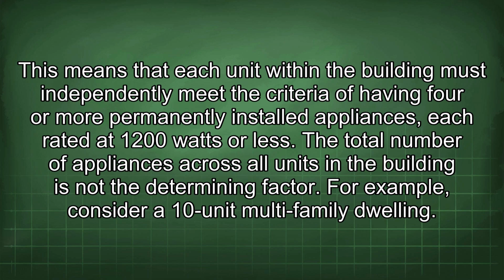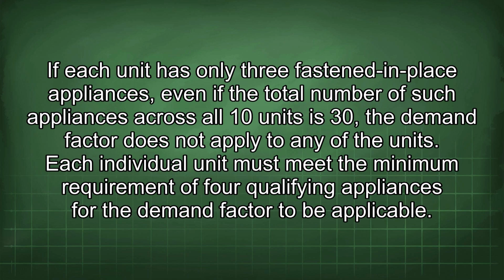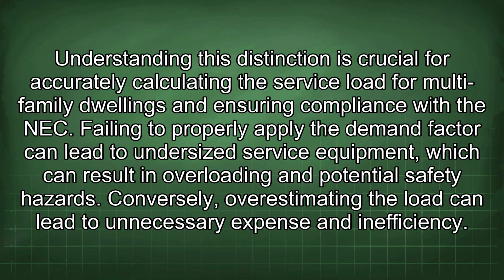For example, consider a 10-unit multi-family dwelling. If each unit has only 3 fastened-in-place appliances, even if the total number of such appliances across all 10 units is 30, the demand factor does not apply to any of the units. Each individual unit must meet the minimum requirement of 4 qualifying appliances for the demand factor to be applicable. Understanding this distinction is crucial for accurately calculating the service load for multi-family dwellings and ensuring compliance with the NEC.